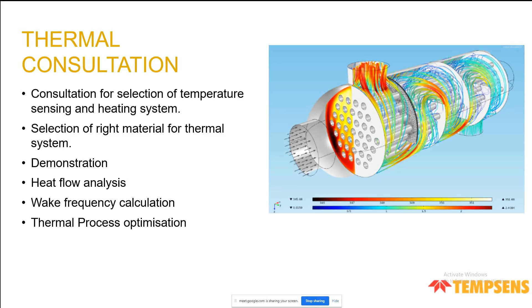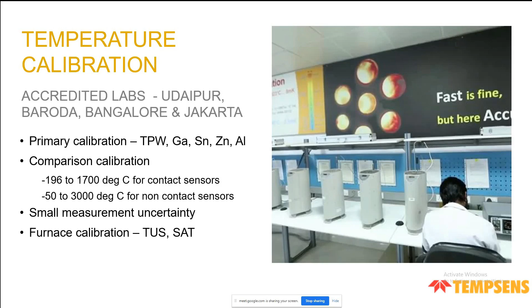We have our calibration labs, three of them in India, which are NABL accredited, and one of them in Jakarta, which is with the KAN accreditation. So we cover a large range, right from minus 196 to 1700 for contact, and minus 50 to, I think I would stand corrected, it is 2900 degrees centigrade for contact type sensor. Also in our Udaipur lab, we have a primary calibration setup with the triple point of water, gallium, tin, zinc and aluminium up to 660 degrees centigrade, right from 0 degrees centigrade. Also we have accreditation for doing on-site calibration. It could be for the sensors, it could be for furnaces, or it could be for some other scope as well, but all related to temperature. Our measurement uncertainty is amongst the best in its class, and I think one of the best in India, and maybe worldwide it is among the lowest uncertainties.